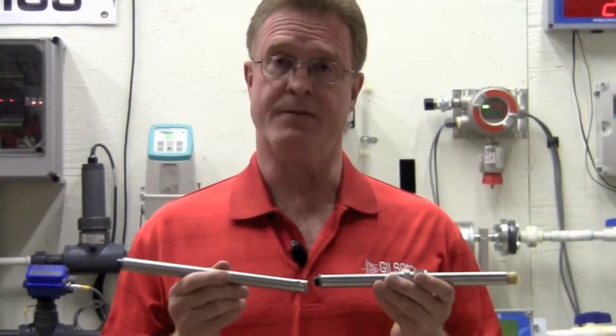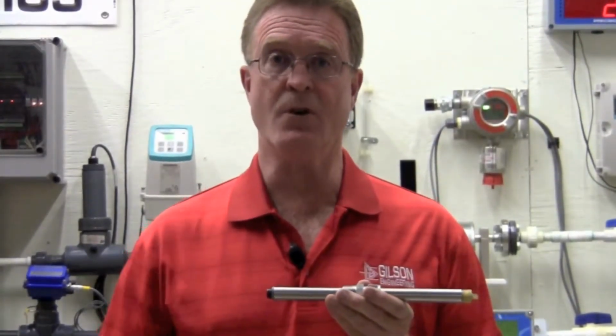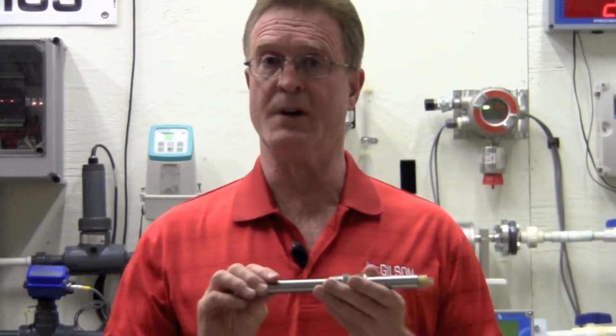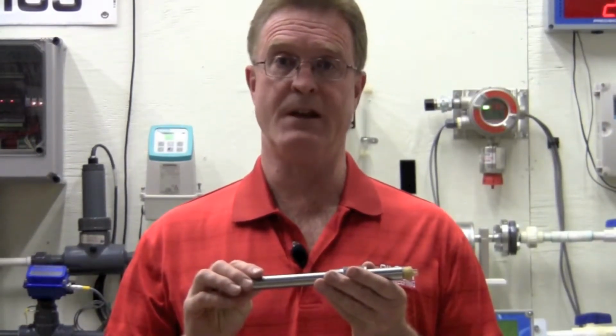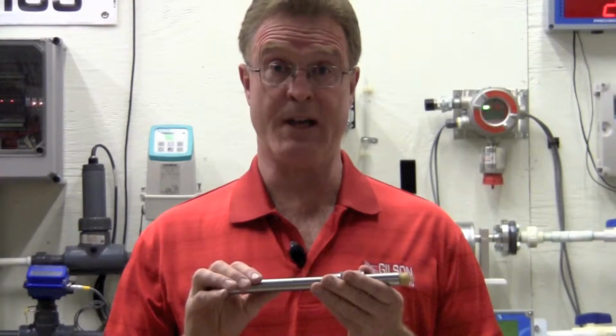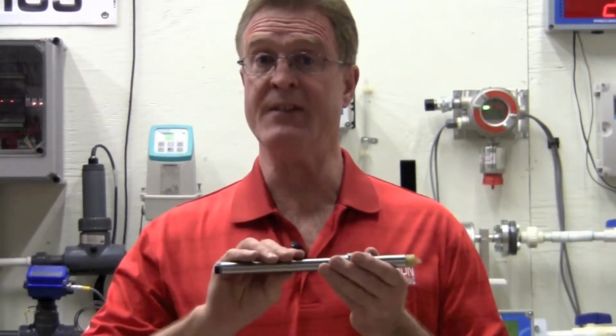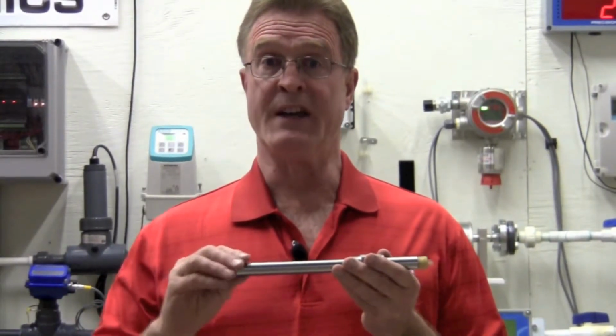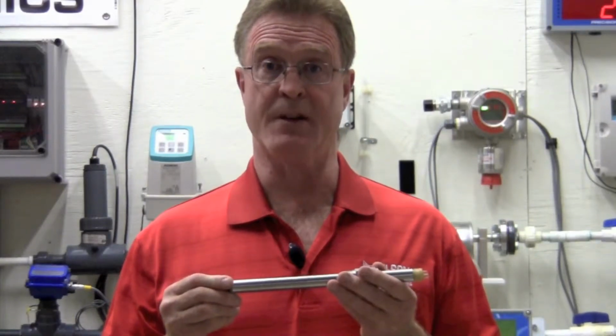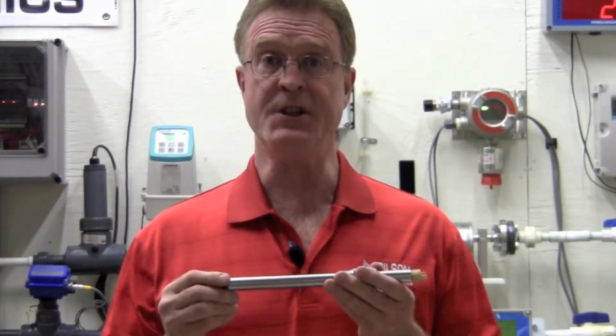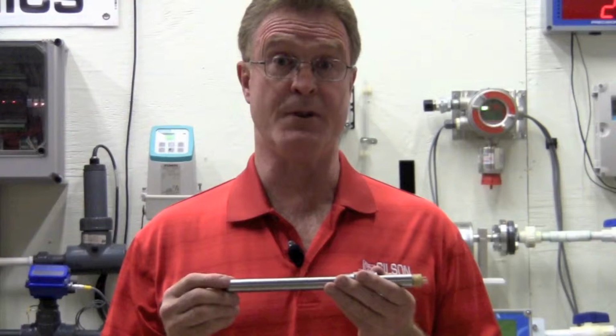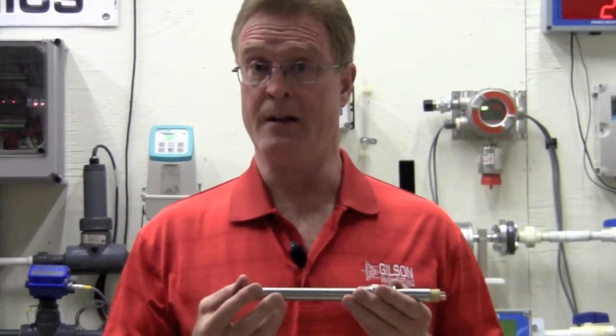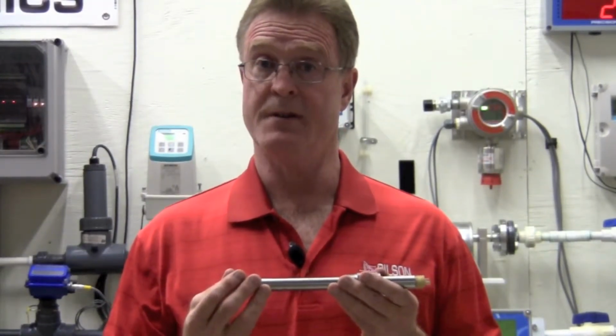The biggest innovation from ECD with the Intelligence series is that the zero and span, the millivolts corresponding to 0, 7 pH, and span, either 4 or 10 buffer, are stored in the sensor. When I connect with the transmitter, the T80, it digitally reads what type of sensor it is and then uploads from the sensor the zero and span values.